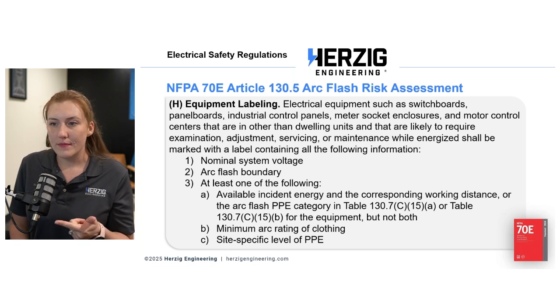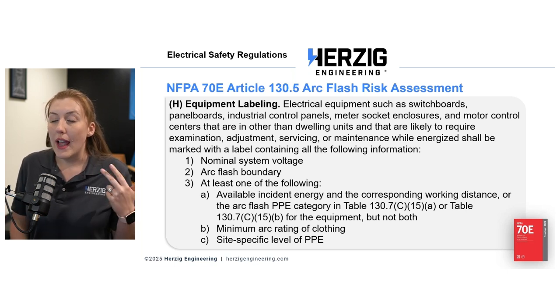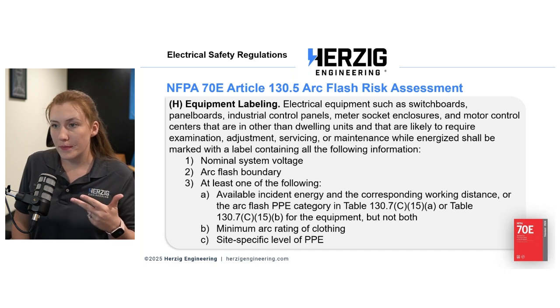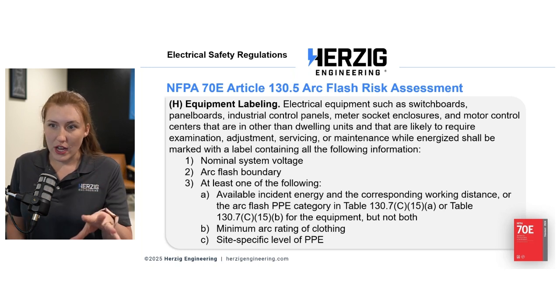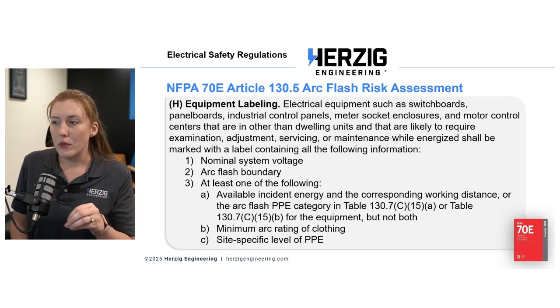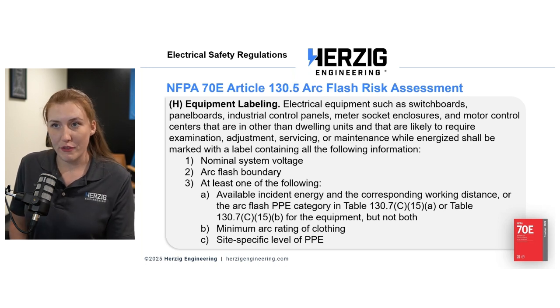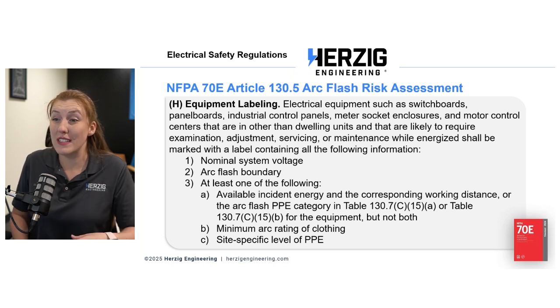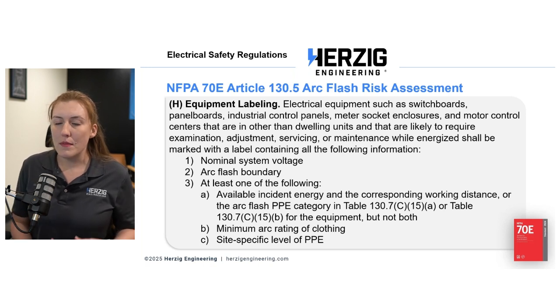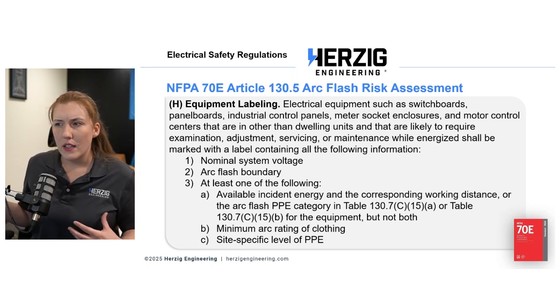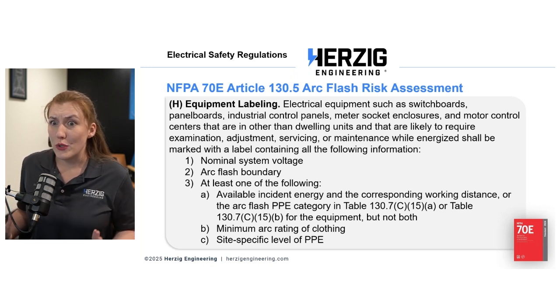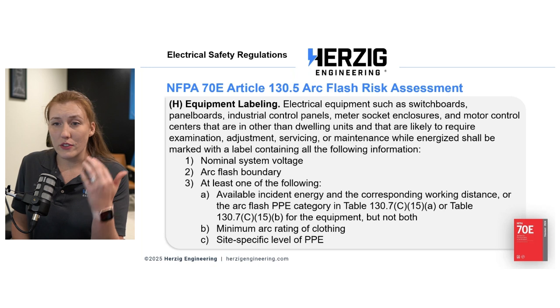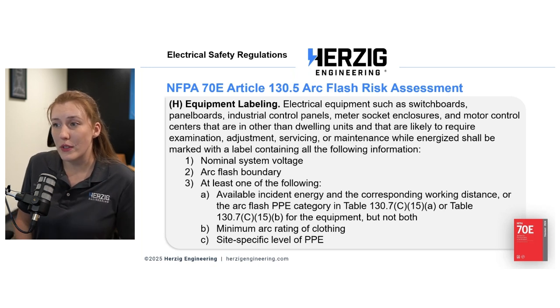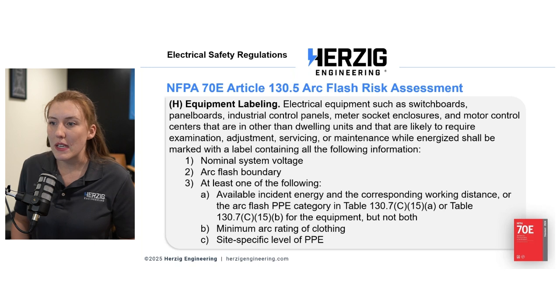The arc flash boundary - how far out can this hazard hurt people, and how are you going to protect yourself within those boundaries? Knowing those three key elements for arc flash and shock hazards is going to drastically simplify your electrical safety training, because if you know what the hazard levels are, it takes out a lot of the guesswork, discussion, and debate about what do we do then. It'll tell you right there, showing you how to protect yourself and others with those boundaries and protection requirements, the PPE, the incident energy, things like that. So they go hand in hand.